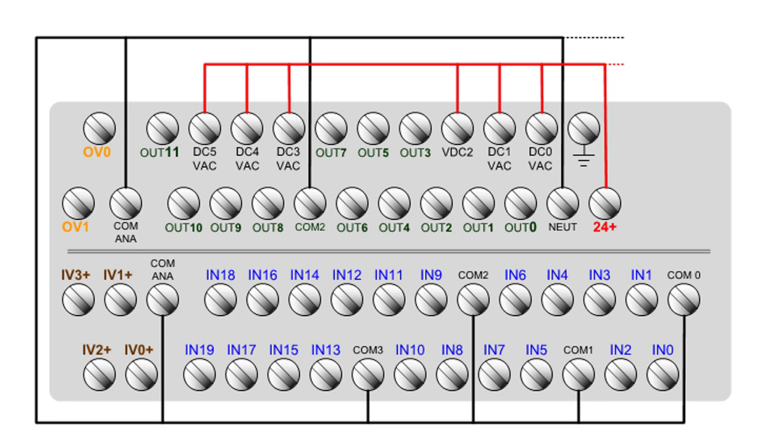And then goes over to common analog on the input side, jumpers to common 3, common 2, common 1, and common 0. And you don't have to do them in that order. You could come in anywhere on any one of those screw terminals and then jumper to all the rest. Now remember, I do it this way because I normally connect all of my commons together to eliminate certain noise characteristics.